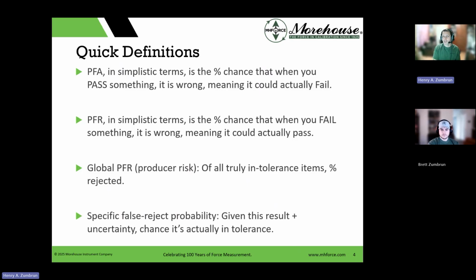So that's the risk of using laboratories with high uncertainties and untrained technicians doing stuff that may not make sense. Does that make sense to you, Brett? Through just my mild level of experience, I know that not every force instrument is created equally for what calibration procedure you need to follow. A single run calibration isn't the same as an ISO calibration. There are different steps, different procedures, and different ways that you interpret the data. It's not one size fits all.